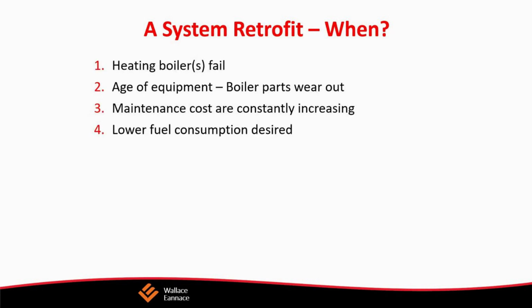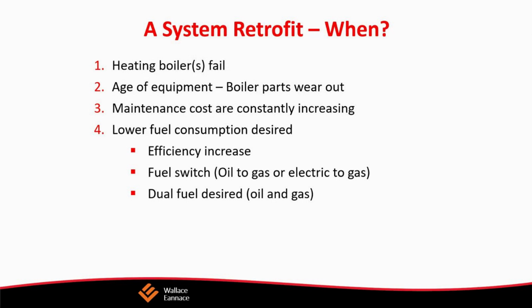And what you're going to find is high flue gas losses going out. You're going to have inefficient system controls and high levels of emissions. Also, with these old boilers, you know how warm they are. They're radiating, with heat going out all along the sides of the boiler. So there are really surface and standby losses, and they can be very significant. And let's face it, to keep these guys running, there's very high maintenance cost.